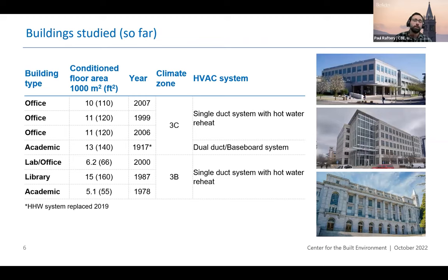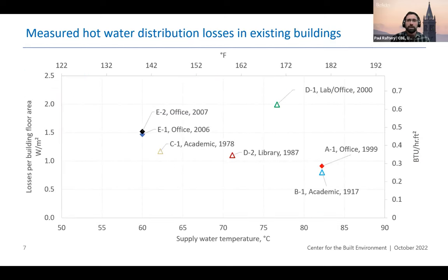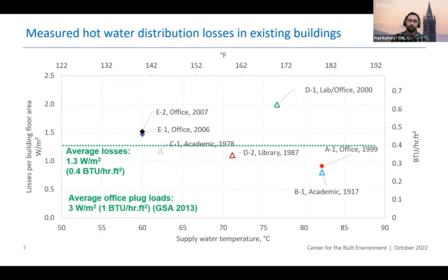We studied seven buildings so far, all in California, but all pretty large commercial or academic office buildings, primarily with single duct VAV systems and hot water reheat. What we found — looking at supply water temperature on the x-axis and losses normalized against building floor area on the y-axis — is a lot of scatter from these seven buildings. But taking the average, the distribution losses from hot water piping is about 0.4 BTUs per hour per square foot. To put that in context, that's about 40% of average office plug loads in the United States according to the GSA. I don't think anyone would characterize that as negligible.